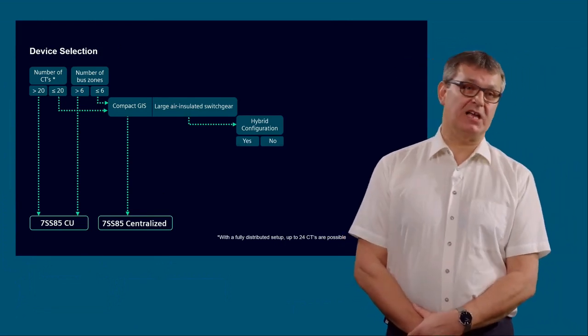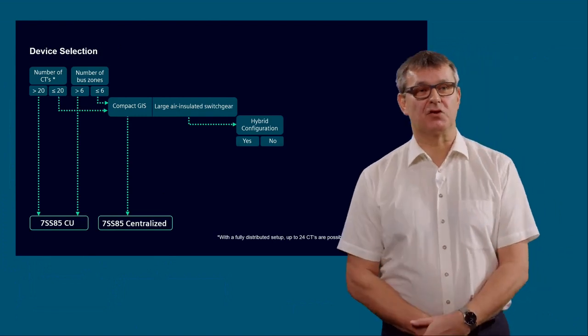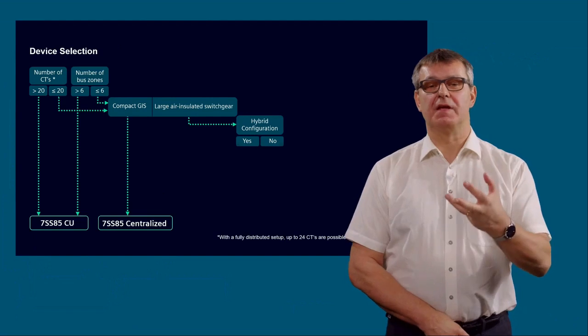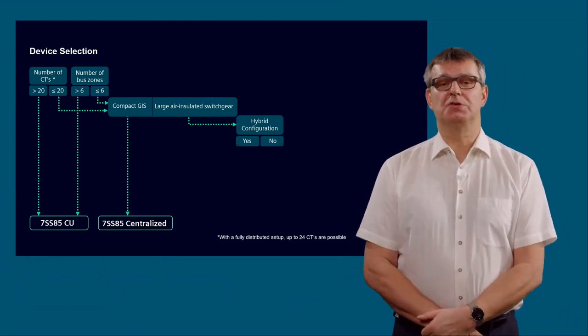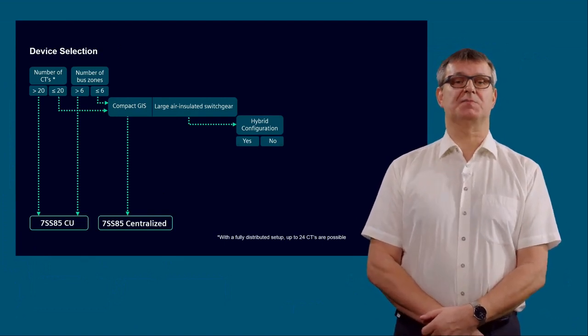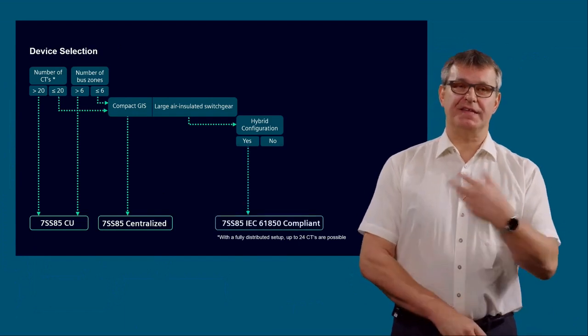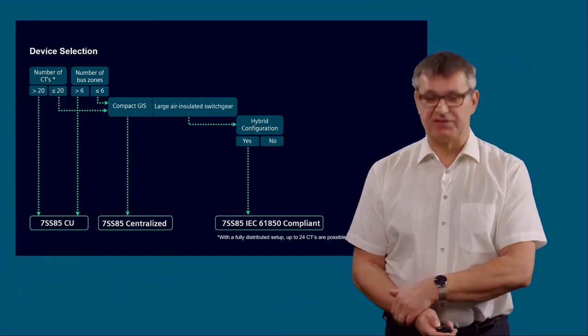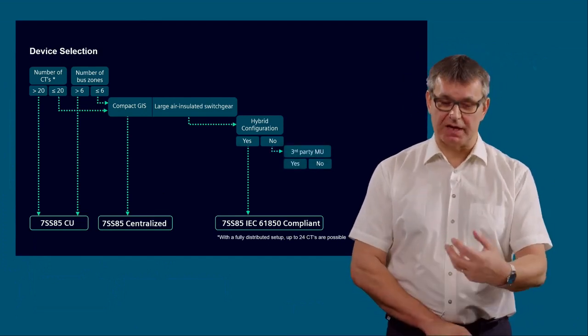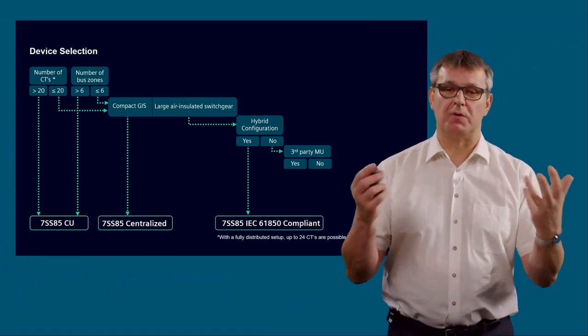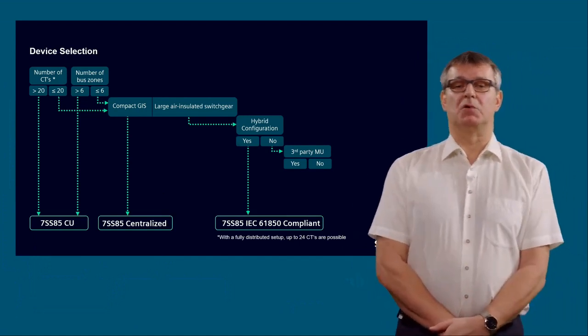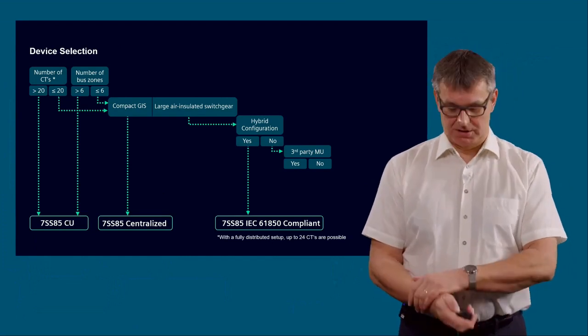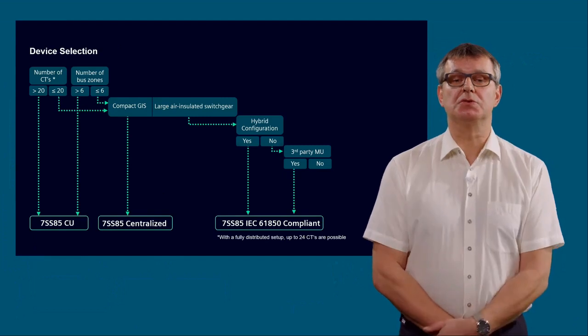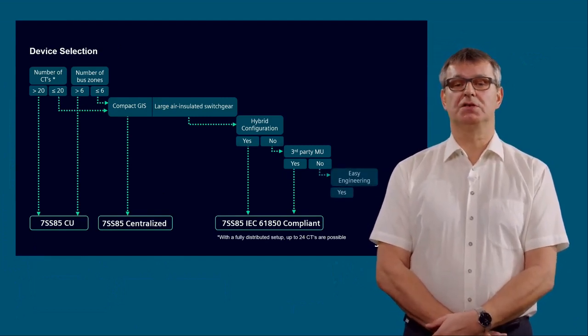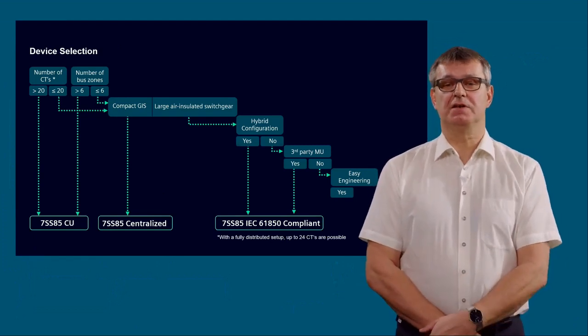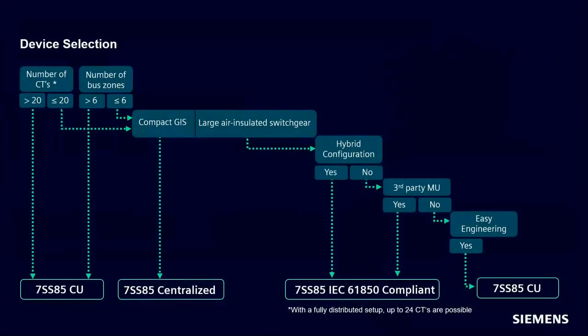Okay, if we have a large air-insulated switchgear, that means we need for sure a distributed busbar protection, and we can ask further questions. Do we want to use a hybrid configuration, a mix of a centralized busbar protection and a distributed busbar protection? If yes, we should use the IEC 61850 compliant solution. If not, then you may ask, okay, do you or the customer want to use also third-party merging units, maybe from NARI, GE, or anything else? If yes, you also only have the chance to use the IEC 61850 compliant solution. If not, and you want to have an easy engineering, you should use the 7SS85 CU solution.